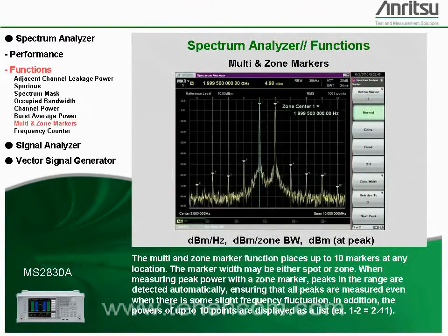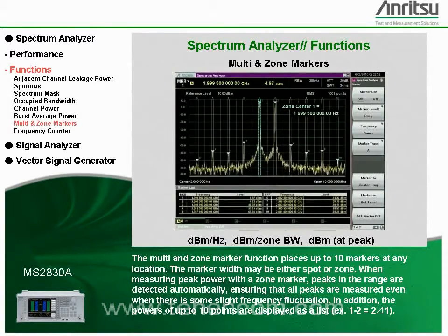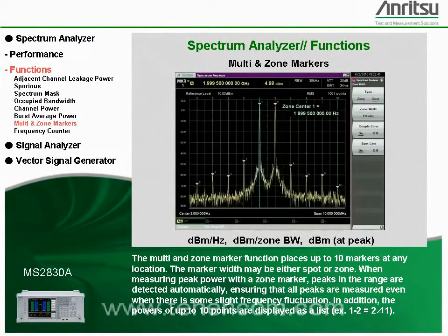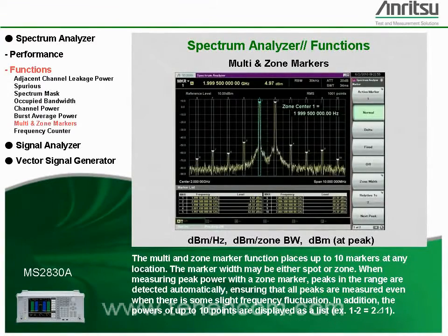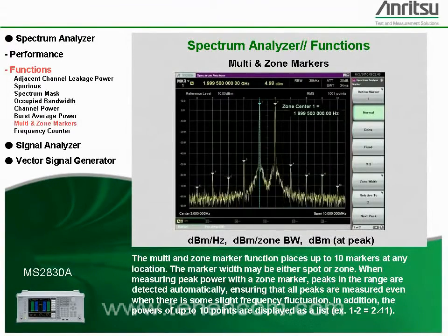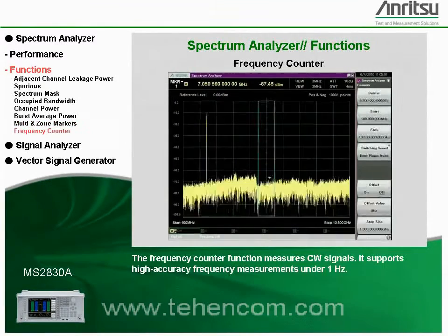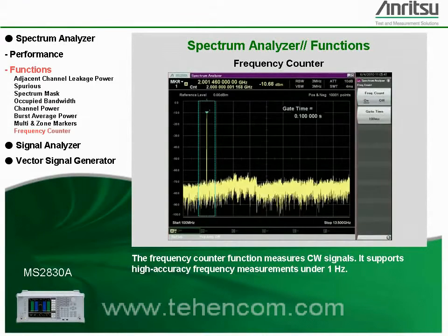The multi- and zone marker function places up to 10 markers at any location. The marker width may be either spot or zone. When measuring peak power with a zone marker, peaks in the range are detected automatically, ensuring that all peaks are measured even when there is some slight frequency fluctuation. In addition, the powers of up to 10 points are displayed as a list. The frequency counter function measures CW signals and supports high-accuracy frequency measurements under 1 Hz.